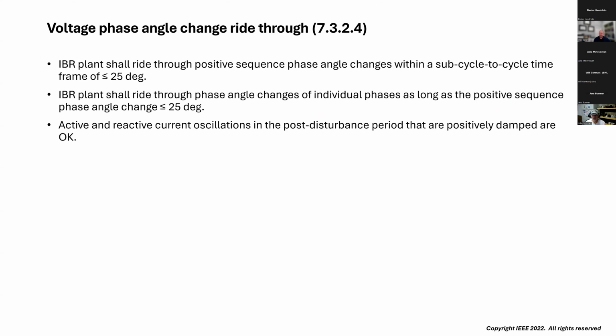And then finally, there's a phase angle change requirement. The key here is that as long as a positive sequence phase angle change, or phase angle jump, is less than or equal to 25 degrees, the IBR needs to ride through. That means that if during, say, an unbalanced fault, some of the individual phase angles change, the plant needs to ride through, provided that the positive sequence phase angle change is less than or equal to 25 degrees. Now, when there's a phase angle change, there's probably going to be active and reactive current changes from the IBR, and so the requirement is for those to be positively damped.